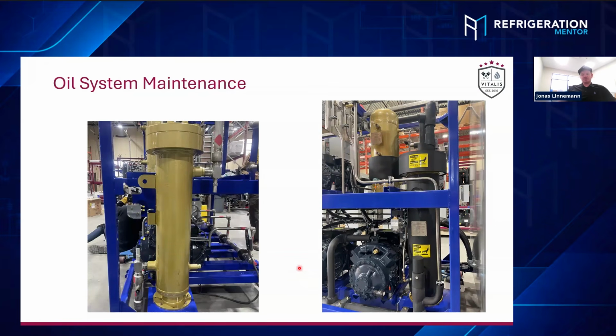If you want to do the maintenance, the cartridge filter change, you can see here 2 service valves. Whenever you do that, switch off your evaporators, let the system pump down properly to shut off the compressor safely, and make sure not to lose your goods in the warehouse, obviously. But once the compressors are shut down, you can isolate this oil separator at the outlet and the inlet.